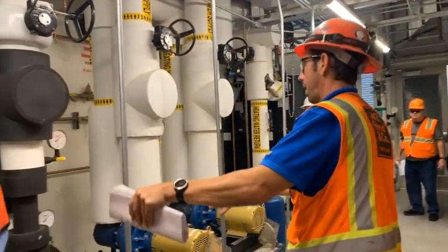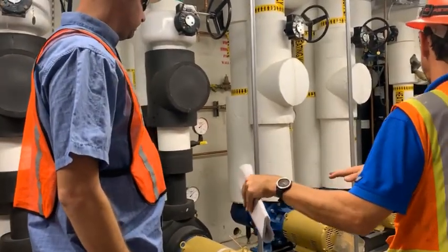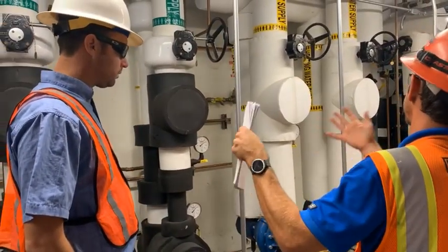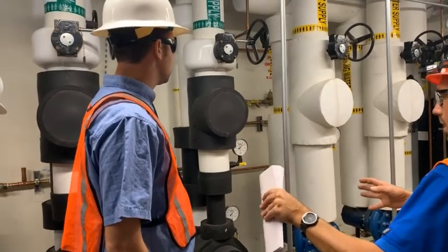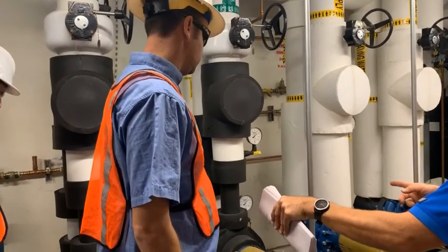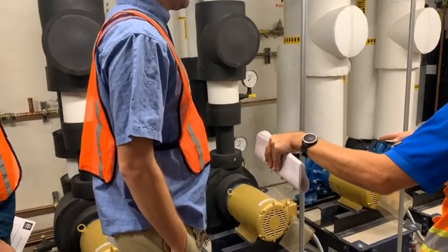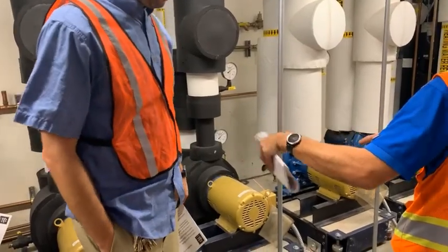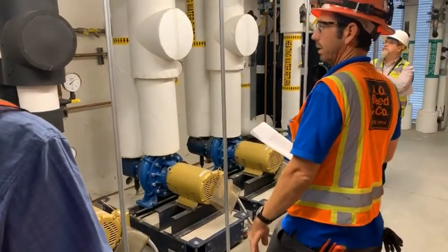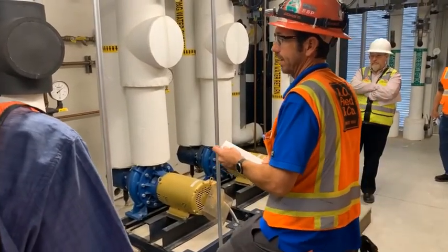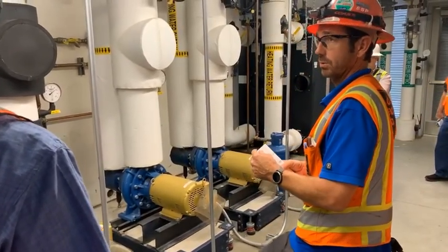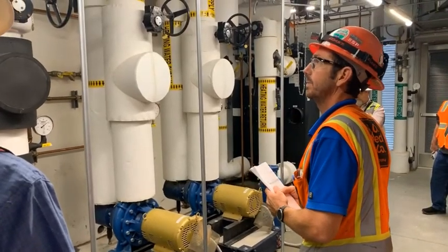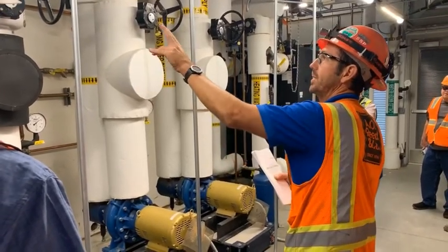We have 2 chilled water pumps. We're kind of going to get into some hydronic. We're still in valves and HVAC, all that good stuff too. 2 chilled water pumps. They're redundant. We can verify that with Doug through his control sequence. And 2 heating hot water pumps. I assume they're redundant also. They are, yes, to the best of my knowledge, but Doug's sequence in the controls will be able to get us that information. Again, each pump has a shutoff valve.